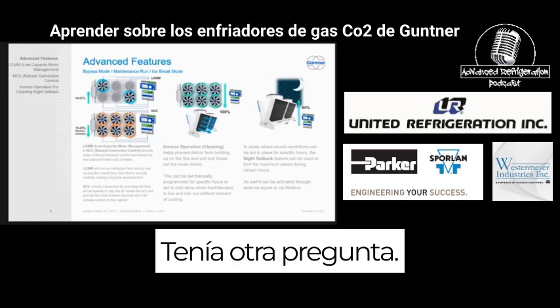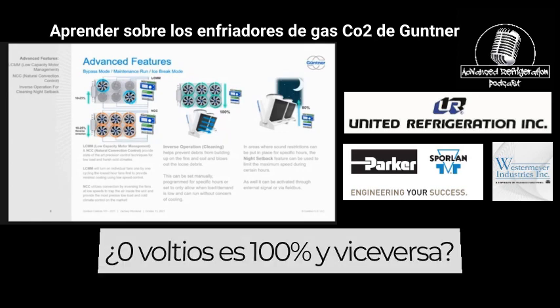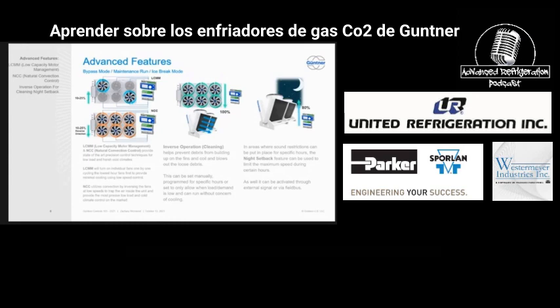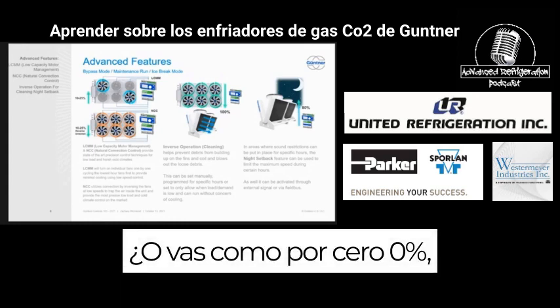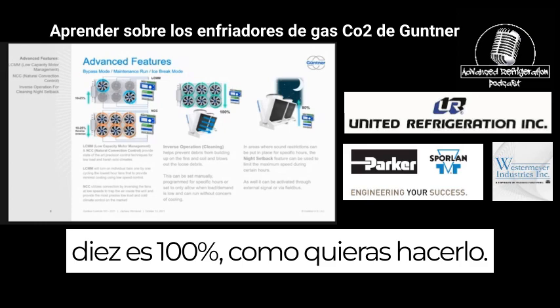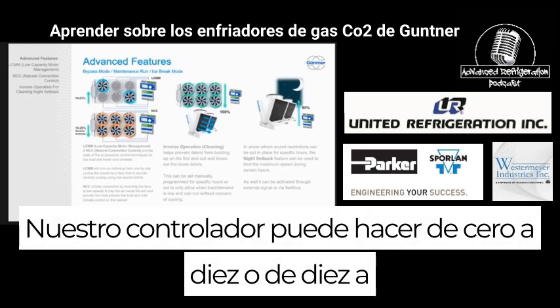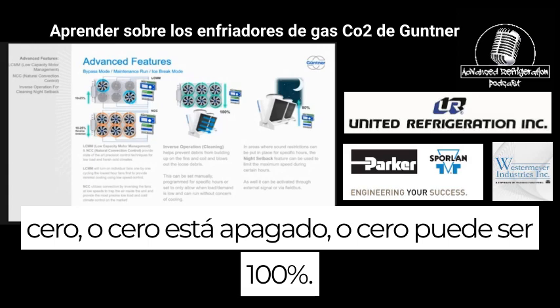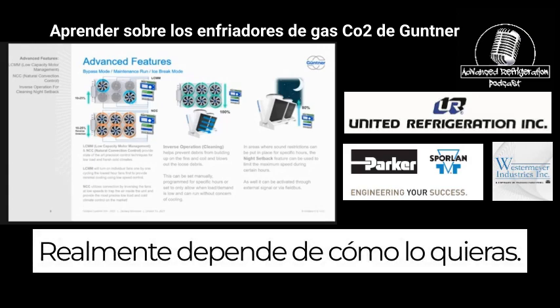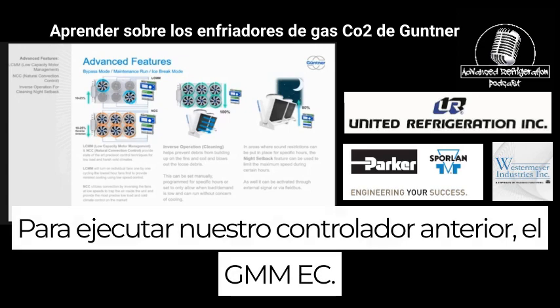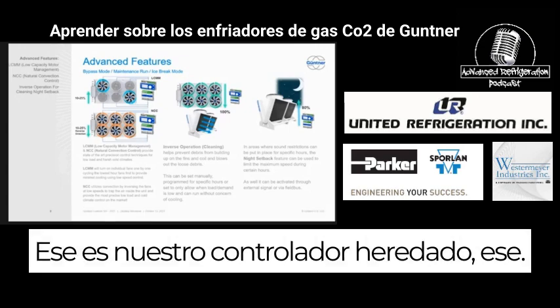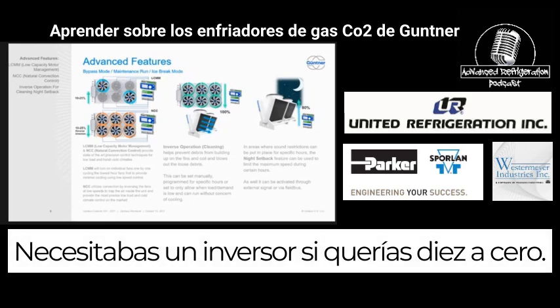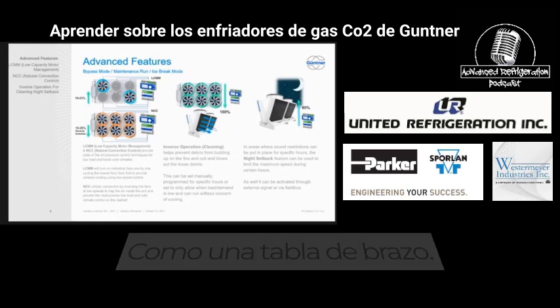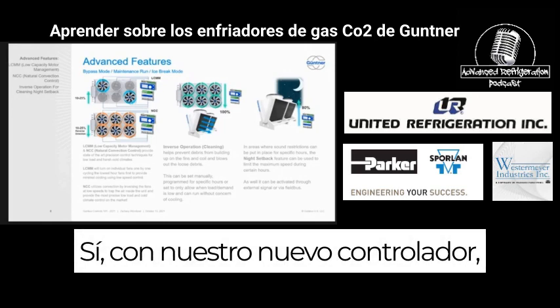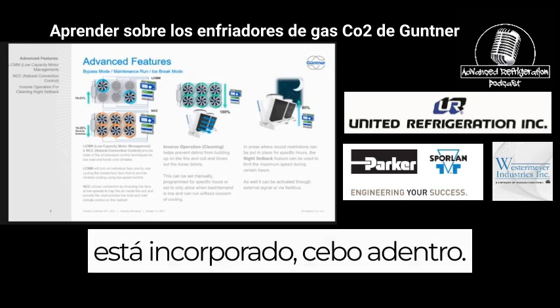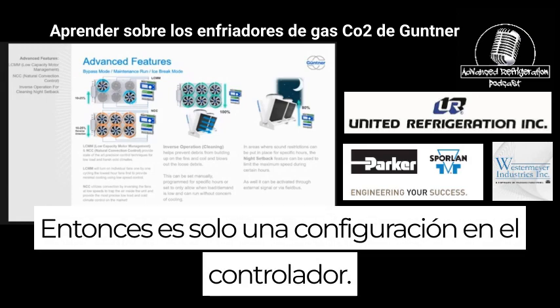I had another question. So are you guys doing the standard zero volts is 100% and vice versa? Or are you going like 0 is 0%, 10 is 100%? However you want to do it. Our controller can do 0 to 10 or 10 to 0, or zero is off, or zero can be 100%. It just really depends on how you want it to run. Our previous controller, the GMM EC, that's our legacy controller. That one, you needed an inverter board if you wanted 10 to zero. With our newest controller, it's baked in. So it's just a setting on the controller.